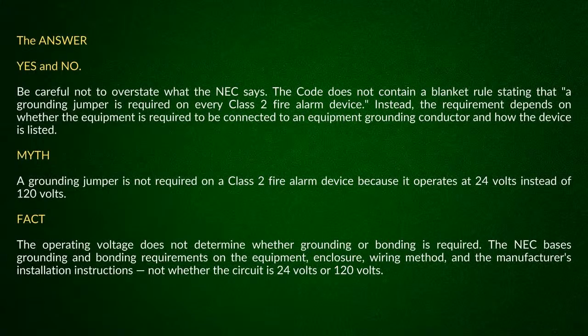And I think that it was a little sketchy the way they had it wired before, because they pulled a full size ground through that wire mold and then they just capped it off. It wasn't tied to anything, you know? Yeah. So to me, that's a code violation, because you have to ensure that path of continuity. And so that would be where that jumper would need to be connected to that equipment ground and bonded to that enclosure. Sure. But in this case, you don't really have any reason to even use it, because it's just 24 volt Class A or Class 2 wiring.